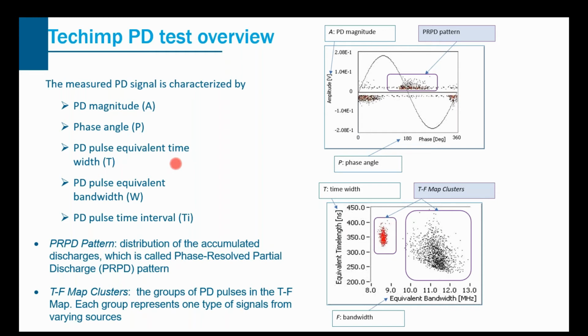Just imagine that we have a short pulse in the time domain, and the pulse width is in the range of a few microseconds or hundreds of nanoseconds. That's the pulse width. Then there is the equivalent pulse bandwidth: corresponding to the pulse width, if we do the Fourier transform, we can calculate the bandwidth. Those two values are correlated, and they can be used to represent a pulse. The fifth parameter is the PD pulse time interval, which is the time difference to the previous PD pulse. That will be very useful for DC PD testing and maybe some other testing scenarios.